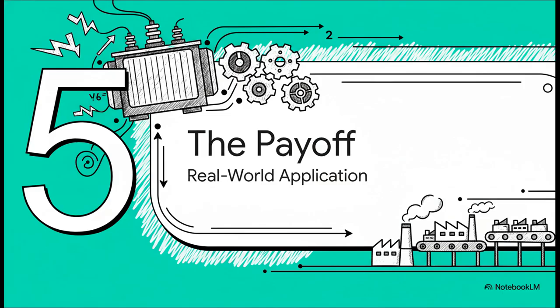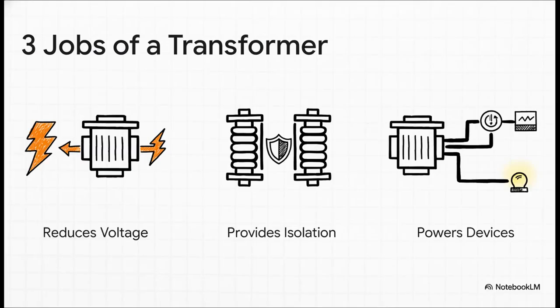Okay, so there they are, our two golden rules. The turns ratio changes the voltage, and the law of power conservation changes the current. Now, let's bring it all together and see why this stuff actually matters out on the factory floor every single day. So really, when you get right down to it, a control transformer is doing three critical jobs for us. First, it reduces the voltage down to a safe level for people to interact with. Second, it provides isolation, creating that literal air gap between the dangerous power and the control circuit. And third, it lets us power standard devices. We can use common off-the-shelf 120-volt parts instead of having to find expensive, custom high-voltage stuff. It really is all about safety, simplicity, and saving money.